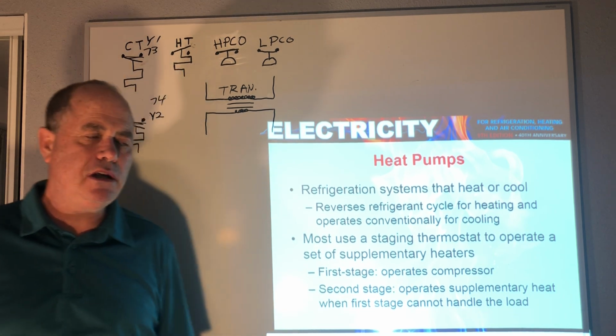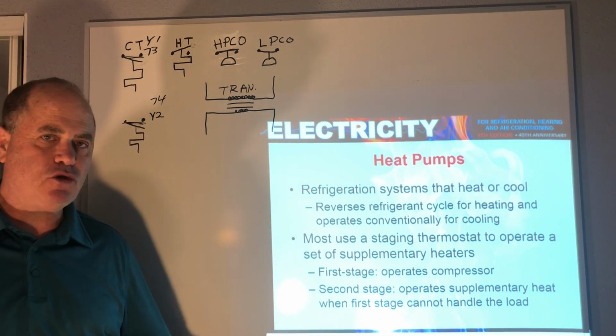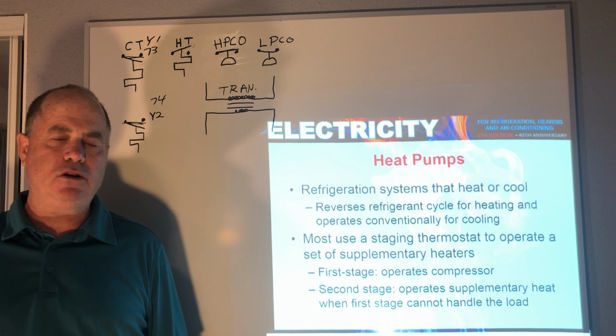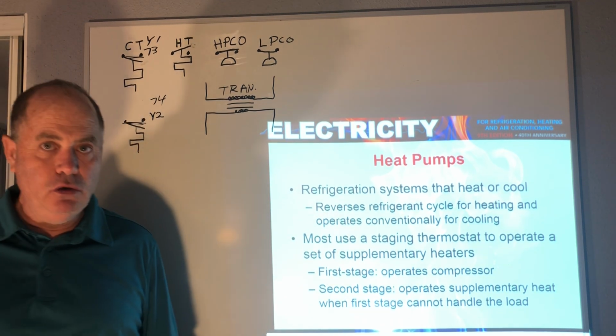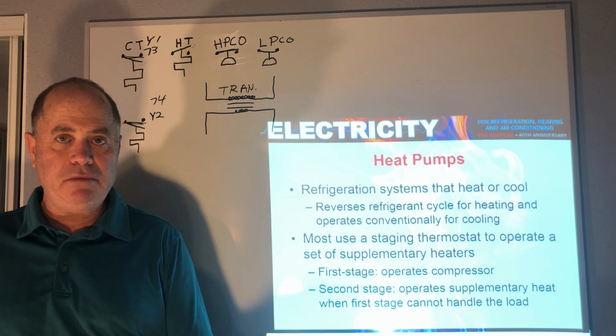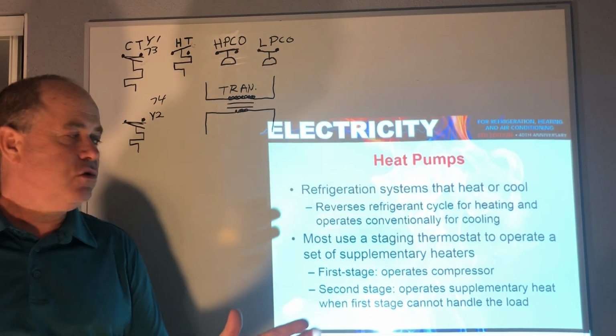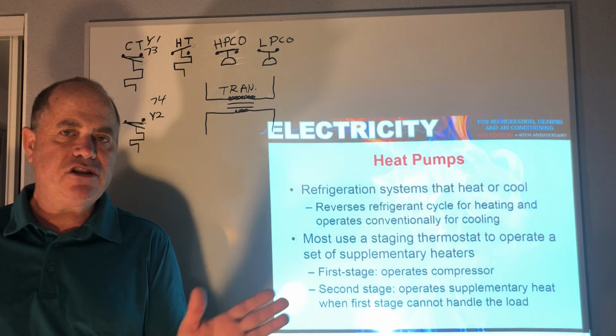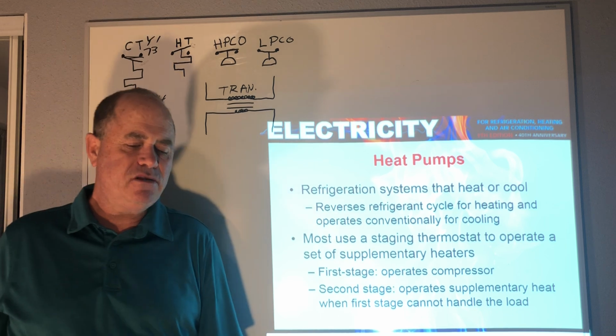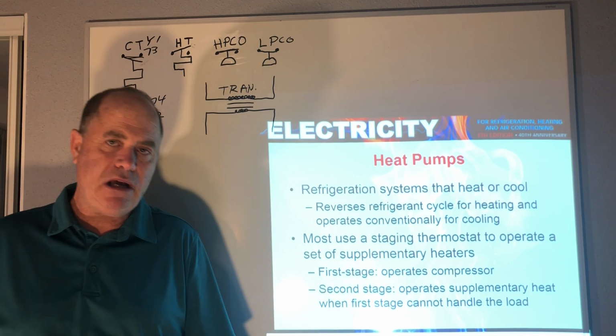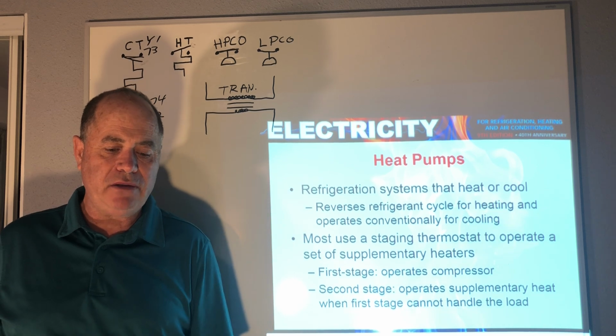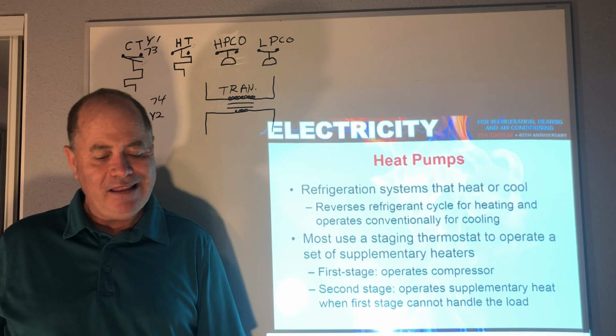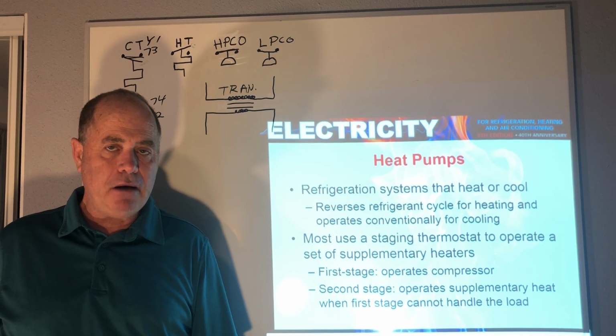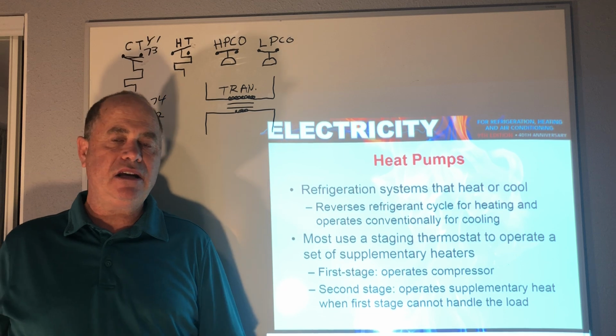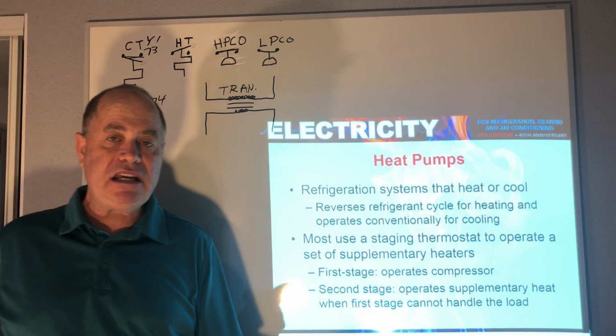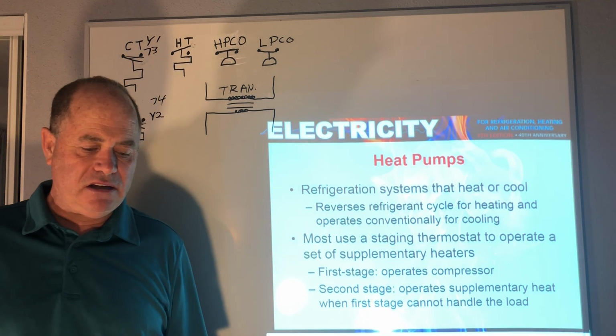Also, because you're running cooling when it's cold outside, you can build ice on your outdoor coil, so we have to kind of go into a defrost cycle, and instead of it flipping back into cooling and blowing cold air on the people, it will do that, but then you turn on those electric heaters to mitigate the cold air so the air comes out neutral and isn't really blowing cold air on the people when they're in the heating mode. Now, that's pretty complicated. Don't worry too much about that just on this one slide, but that's kind of an overview of heat pumps with W1 and W2. And again, the electric strip heat can be used as supplemental heat and also during the defrost cycle.